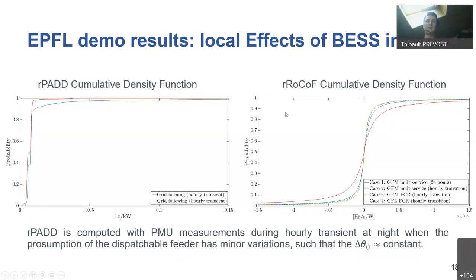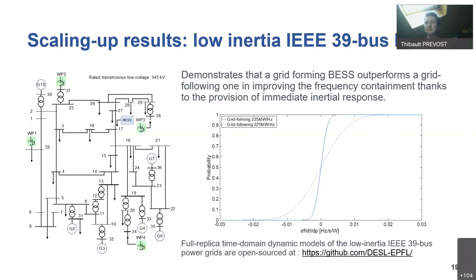Here is the difference between, so let's focus on relative RoCoF. We see that if you have a grid forming type of control, you have a much steeper curve around zero, which means that in fact the frequency has been smoothed a lot and you just have very low RoCoF. So this is based on PMU measurements during, for example, hourly transients that occurred every hour in Europe. But they also did more tests on a real time model. So it's based on the IEEE 39 bus. It's available if you wish at this web address. And here we also see that we have a much steeper curve if we go on grid forming. So one way to discriminate would be, for example, to have a shape here and ensure that your unit will not be as steep as the required one.